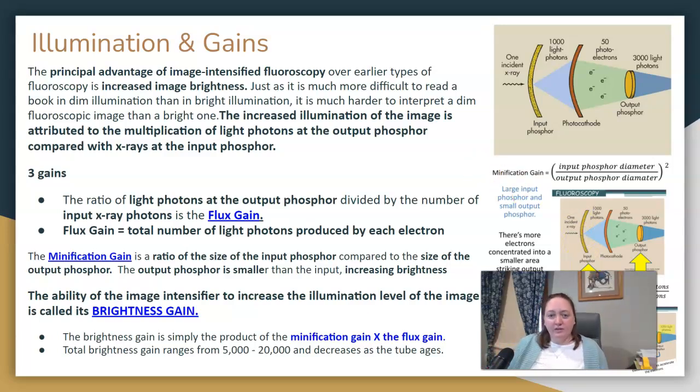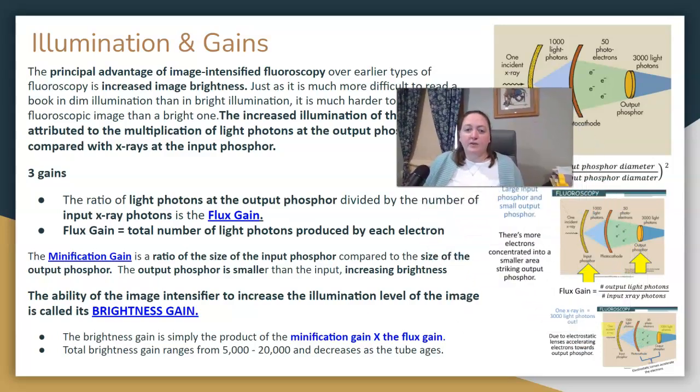And then these two calculations will help us find something that's called brightness gain. Brightness gain, we are simply going to multiply what we got for minification gain and what we got for flux gain. The total brightness that we gain ranges from about 5,000 to 20,000. This will decrease as your tube ages.